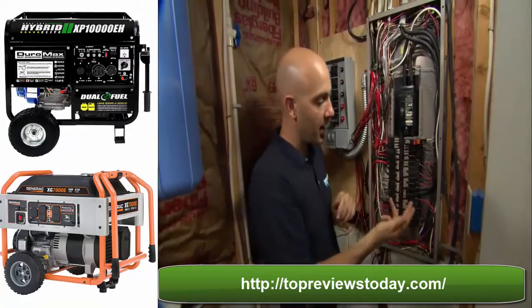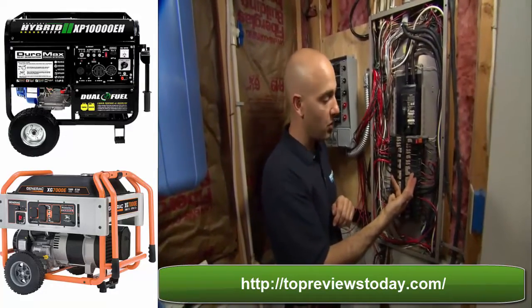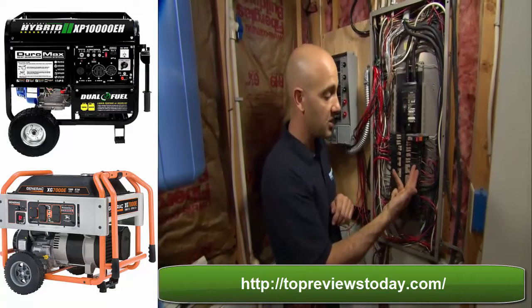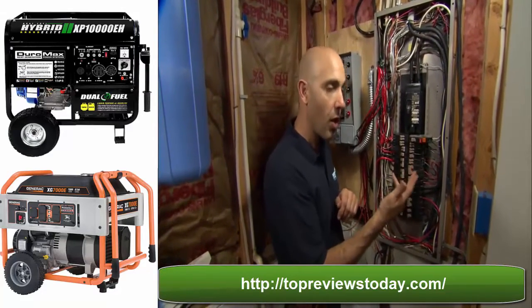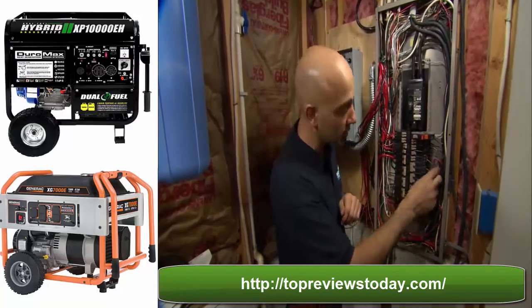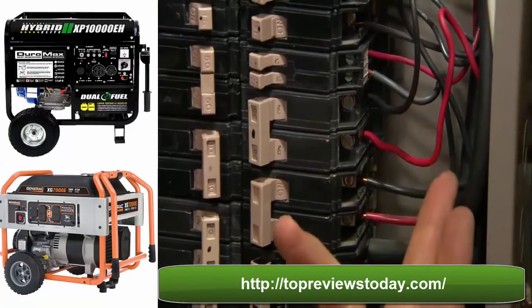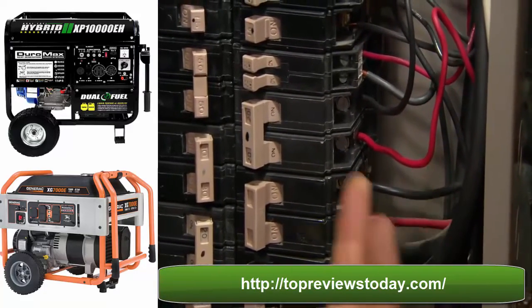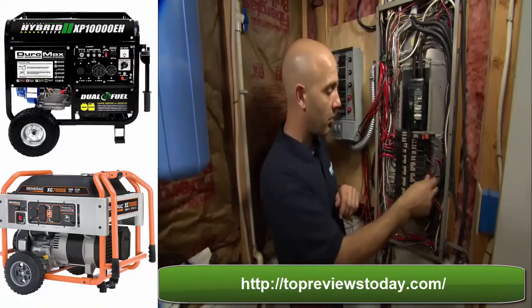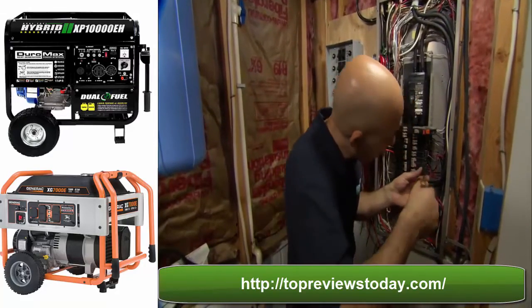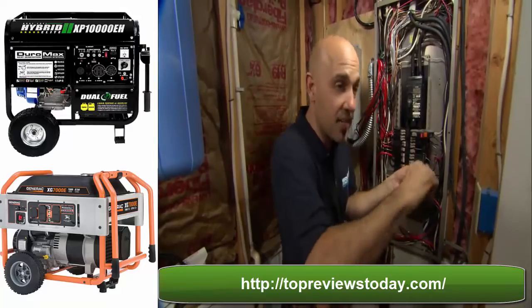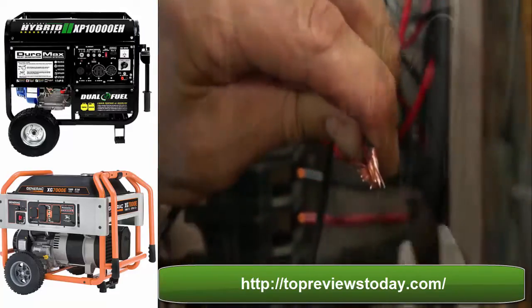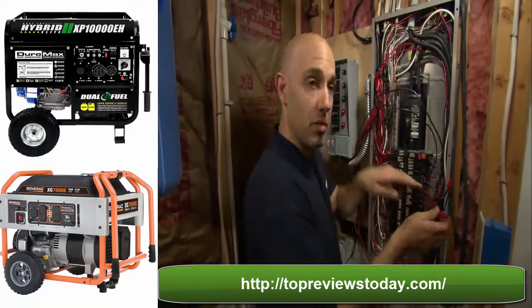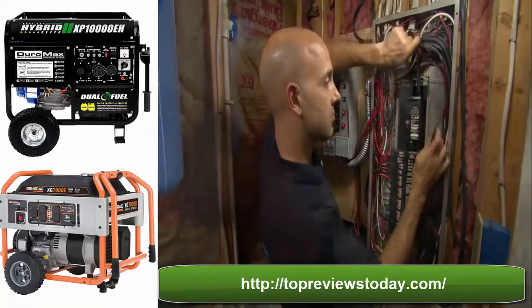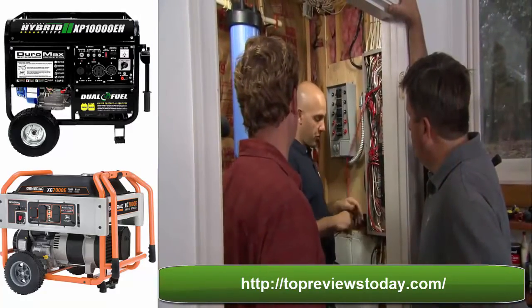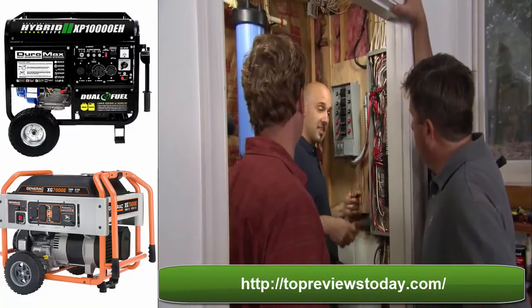All right, so what we have here is a circuit breaker that goes to your well, takes up 2 spots. It's 240 volts, and there's 2 hot wires that go down to your well, 120 volts on the black, 120 volts on the red. So I'm going to go ahead and take these off the circuit breaker and tie them onto the transfer switch, which has the exact same setup. Now we have 240 going down to your well. So we have one more 240 volt circuit. We're going to tie in the exact same way.